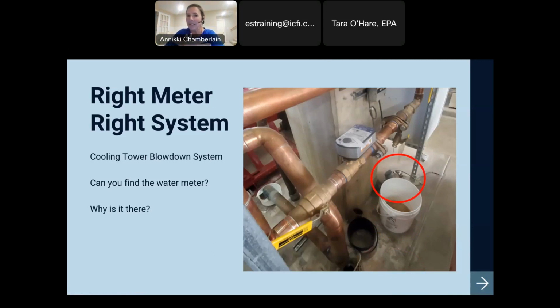It's an open system. You're going to have really high mineral concentration, dirt, twigs. There's one place that I work that every time that the grounds guys mow the lawn, the filter clogs up full of grass. So with cooling towers, I never put anything in the blowdown that has anything in the channel. So it basically always has to be ultrasonic. So these guys just finally got so tired of dealing with it clogging up, they just took it out. So right meter for the right system, whatever it is you're dealing with.